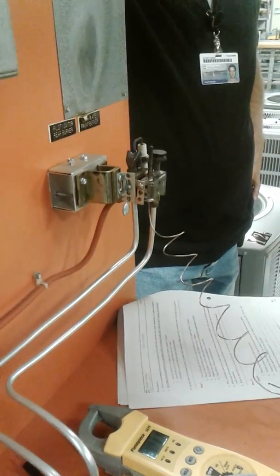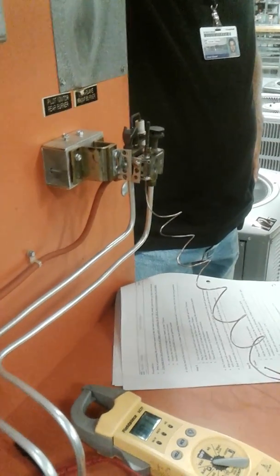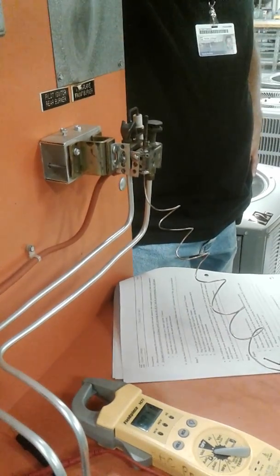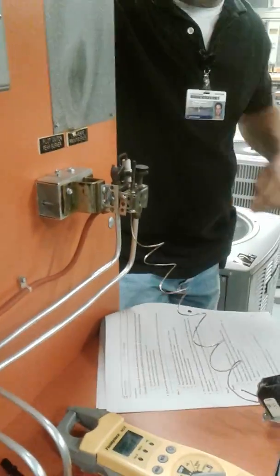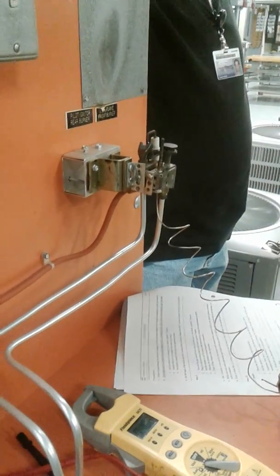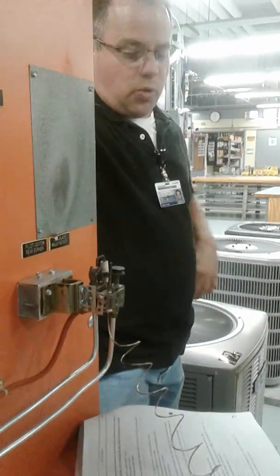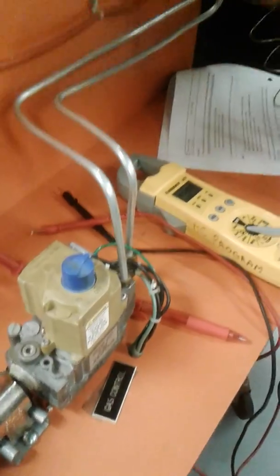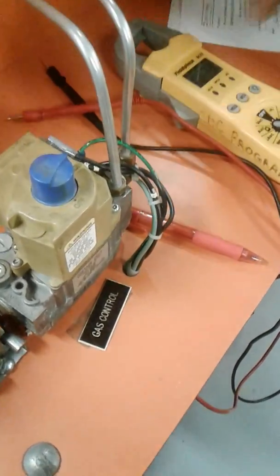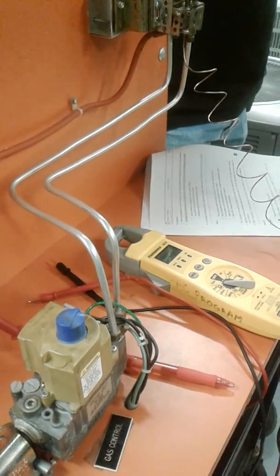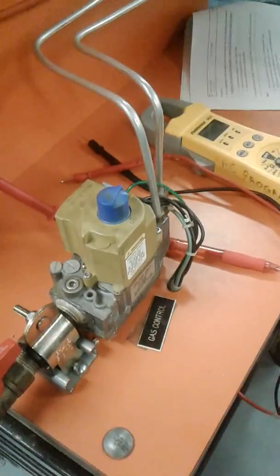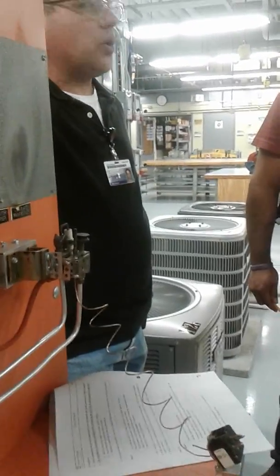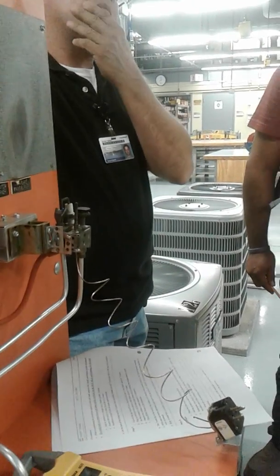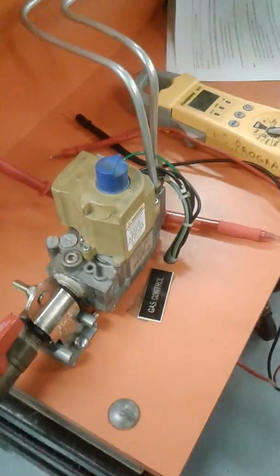We're trying to light. What's happening? It's getting voltage to create a spark, because we're getting our voltage to travel through here to create our spark. Pilot valve. So the pilot's not opening. So if we're getting 24 volts to our PV, MV, and MVPV, so if we're reading 24 volts to our pilot down there, what's happening now? And it's not allowing gas to flow. There's power. What's that? The gas valve itself. He's right. The solenoid is not working. You guys are right.